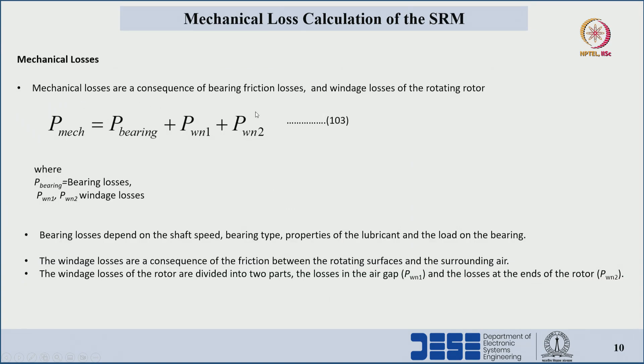Mechanical losses equal bearing losses plus windage losses. The bearing loss depends on shaft speed, bearing type, properties of the lubricants, and load on the bearing. Windage losses arise from friction between the rotating surface and surrounding air, and are divided into two types: loss with respect to the air gap region, and loss with respect to the end region of the rotor.